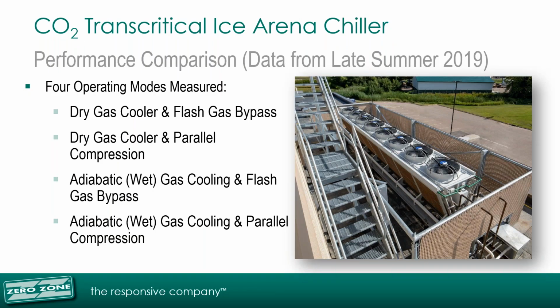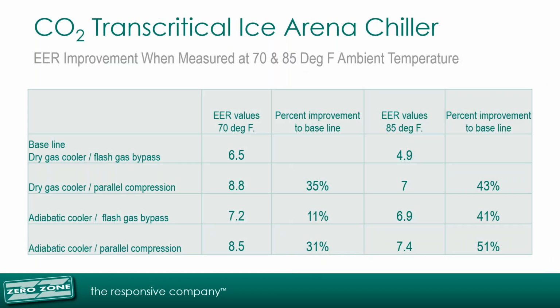4 operating modes were evaluated for about a 1-month period of time. They included dry gas cooler and flash gas bypass operation, dry gas cooler and parallel compression operation, adiabatic wet gas cooling and flash gas bypass operation, adiabatic wet gas cooling and parallel compression operation. In analyzing the system performance, we used watt meters for energy consumption and pump curves to determine the amount of cooling so we could calculate the EER. Performance improvement was calculated against the baseline of a dry gas cooler operating with flash gas bypass.